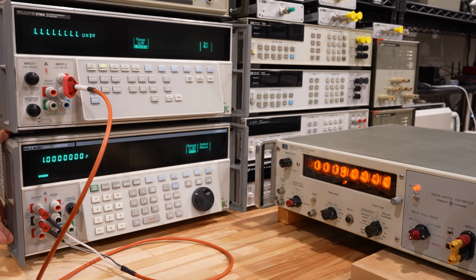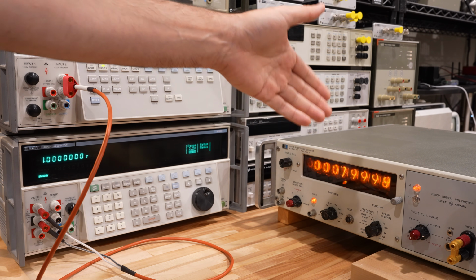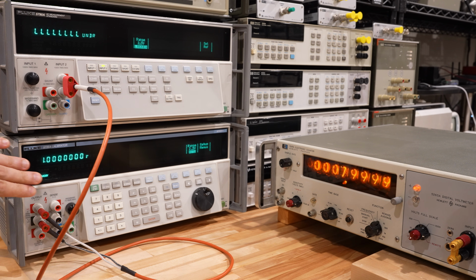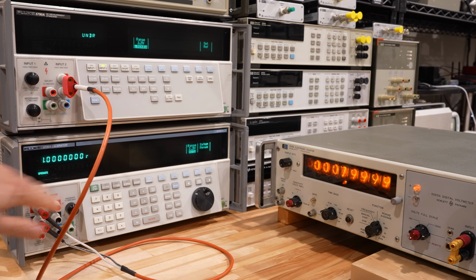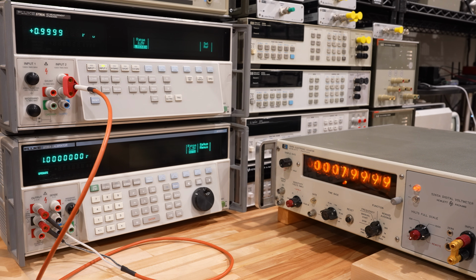At the bottom I have the Fluke 5720A. We're going to generate some voltages using this all the way up to 1000 volt, which is full scale for that, and measure that. And over here we have the Fluke 5790A. This is just to measure this voltage to show us that it is actually working. So let's start with 1 volt. That only has a 10 volt as its minimum input range there. So at 1 volt we're going to enable that. And we should see something really close to 1 volt at the top there.